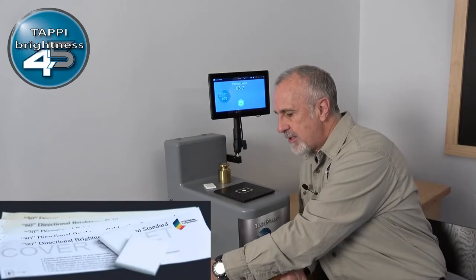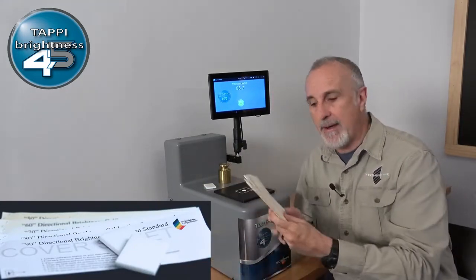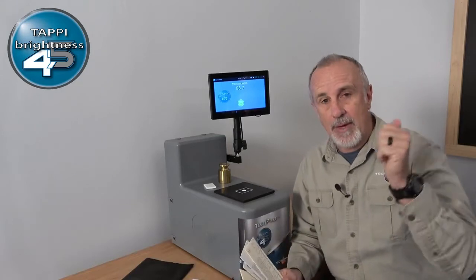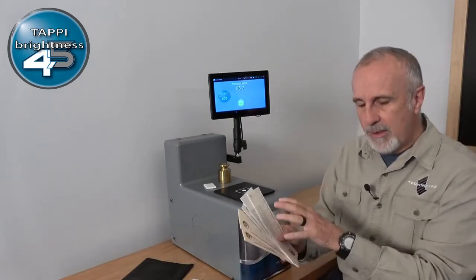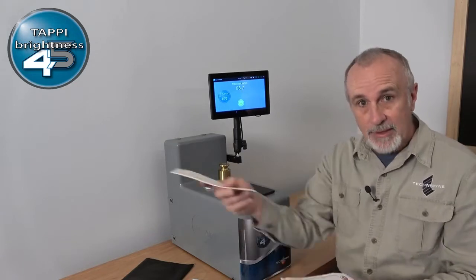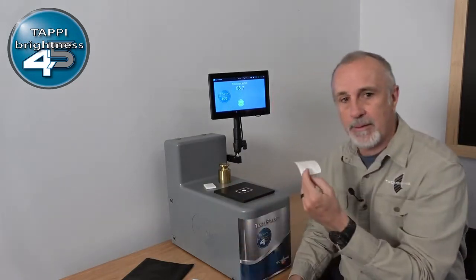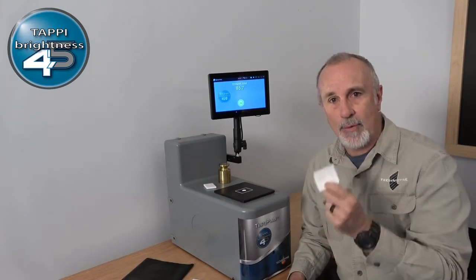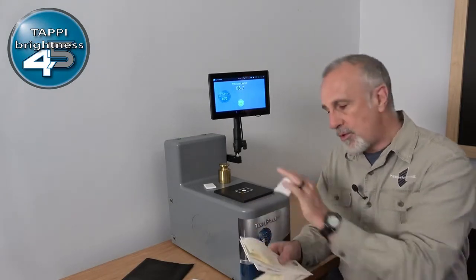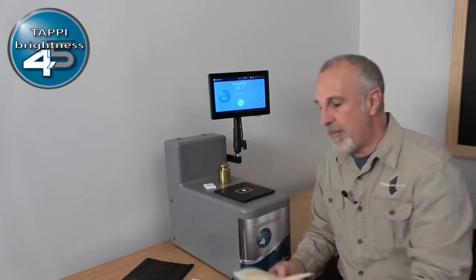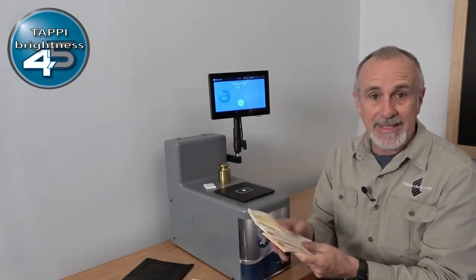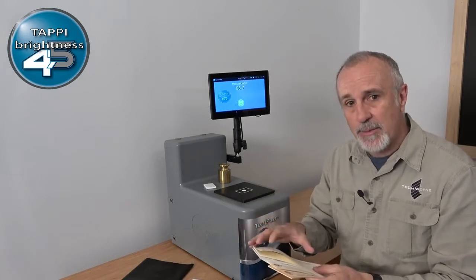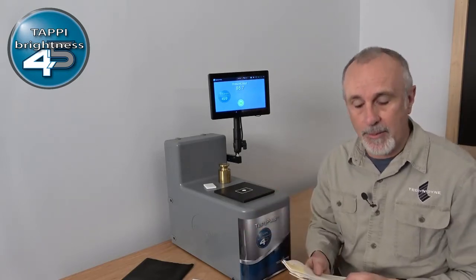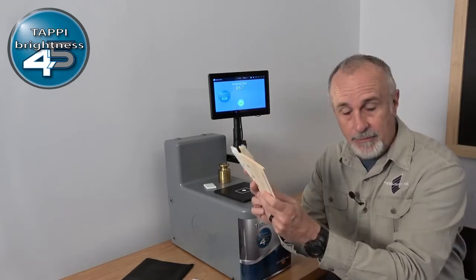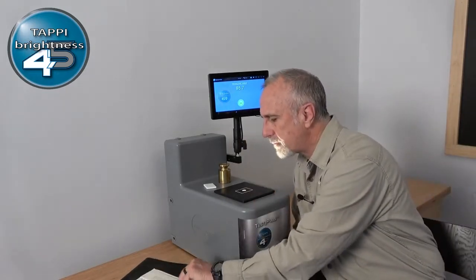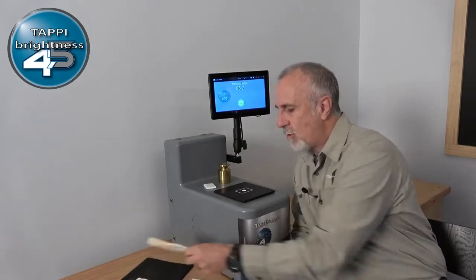And then you'll need a fresh set of paper calibration standards. These standards have all been evaluated back in our master's lab. We load them onto the master instrument, get the values for those, and record those values on a printout that we send along with the standards, so that once you get the instrument in calibration, you can then measure this range from 50 to 90 to check the linearity of the instrument, to make sure everything is good across a broad spectrum. So you get a set of 5 different standards with that. Now on the standard, that's changed a little bit, as you know, over the years.